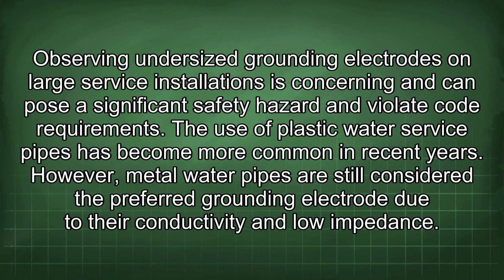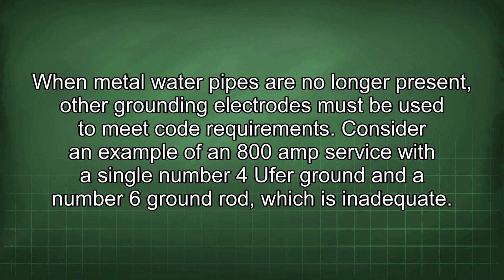However, metal water pipes are still considered the preferred grounding electrode due to their conductivity and low impedance. When metal water pipes are no longer present, other grounding electrodes must be used to meet code requirements. Consider an example of an 800 amp service with a single number 4 Ufer ground and a number 6 ground rod, which is inadequate.